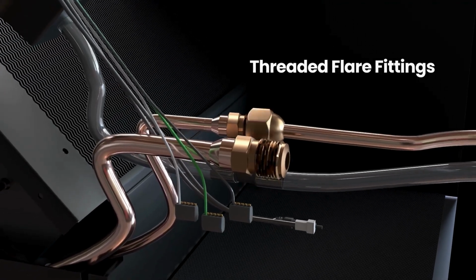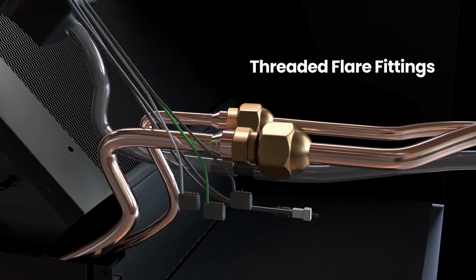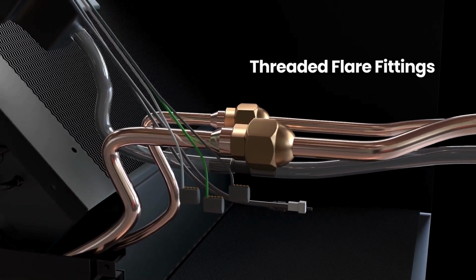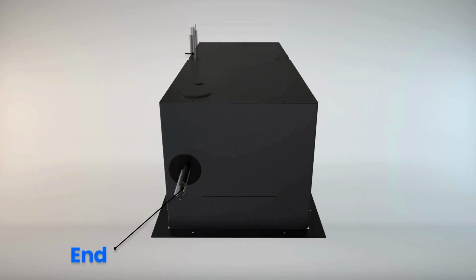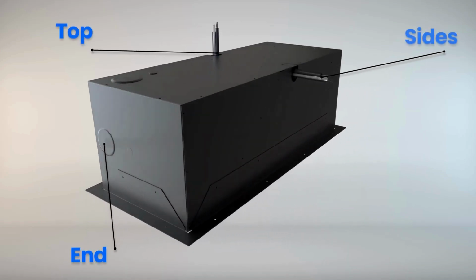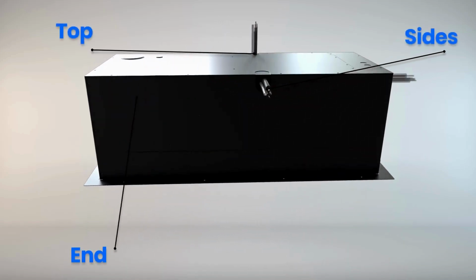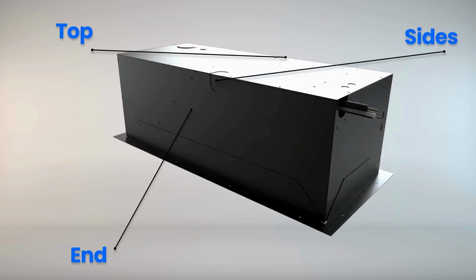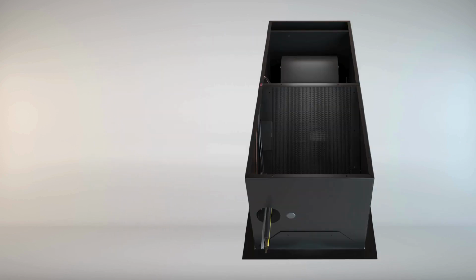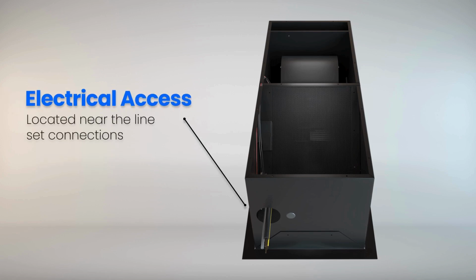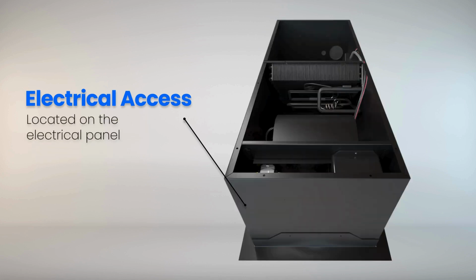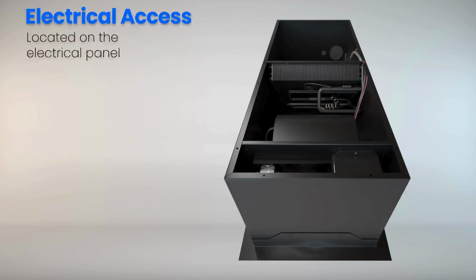The system utilizes threaded flare fittings for line set connections, conveniently located near the cutouts placed on the unit housing for proper alignment, eliminating the need for brazing. Additional knockouts are available on the unit for line set routing. The electrical power source, display cable, bottle probe, and 24-volt communication wire connections are located near the line set connections or on the electrical panel, depending on the unit model.